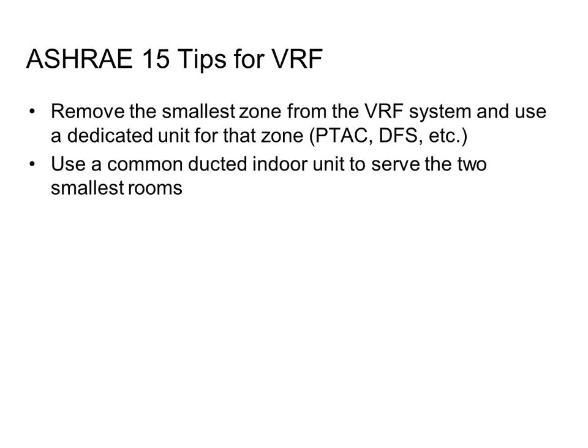The next thing you can do is combine some small zones. If I have two small zones and I combine them into one with a ducted unit, I've just doubled the volume of space that I'm concerned with, right? So obviously half the refrigerant would leak into one zone, half would leak into the other zone, so I would have less of a concern. So I can do that. The penalty, obviously, is now I have one thermostat for two zones, right?